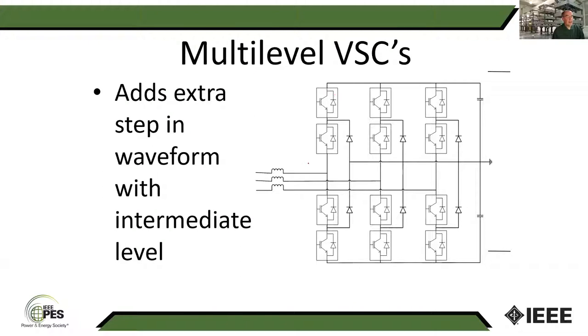To try to improve that, people have come up with modified topologies. So one is a multi-level voltage source converter. By adding what's called a clamp diode here, we're putting in an extra step so the voltage starts looking like this. And by putting this extra step in, every time you do a switch transition, you're only switching half of the voltage instead of all of it. So it cuts the switching losses in half. By putting this extra shoulder in, you're also reducing the harmonics without having the switches at higher frequency. So this topology was actually developed for railroad locomotives originally in Japan, but has seen a lot of use in the last 5 years in things like photovoltaic inverters and wind inverters.